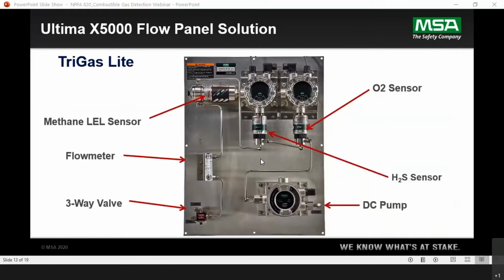So there's the panel itself. This is the panel we used for the WEFTEC show. And interesting here, we've got a picture of it, but basically flow from the filter at the wet well, for example, will come through this 3-way valve, through the flow meter, through the infrared methane detector, through the H2S sensor, to the oxygen sensor, and there's the pump back out to the outlet. So it's a really basic, simple system. Very simple, I should say, versus complex. And we will offer an engineering drawing that shows how we build this with an order.